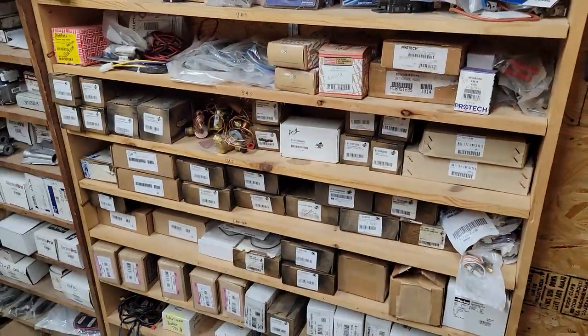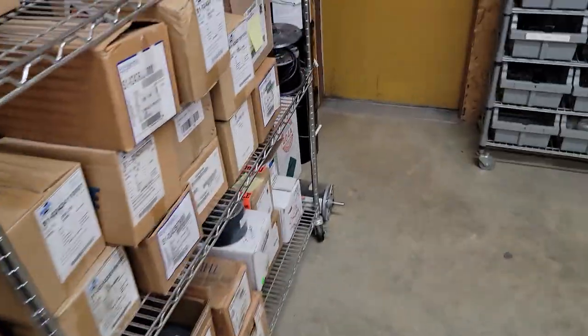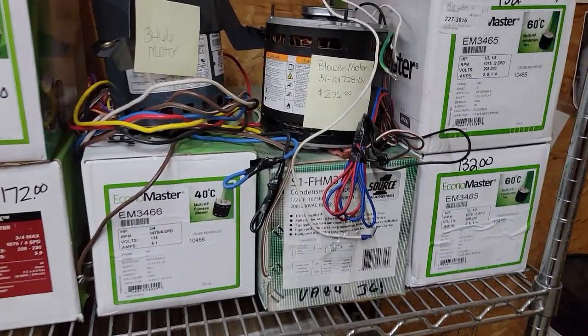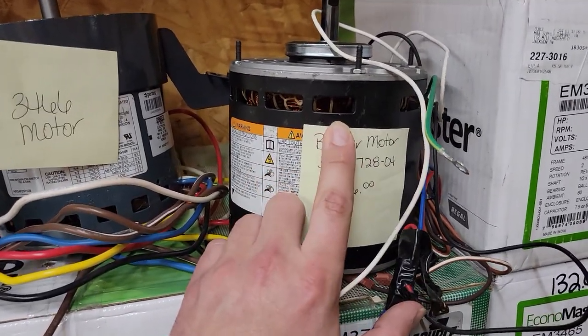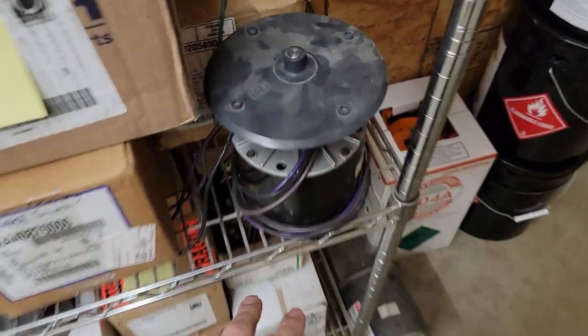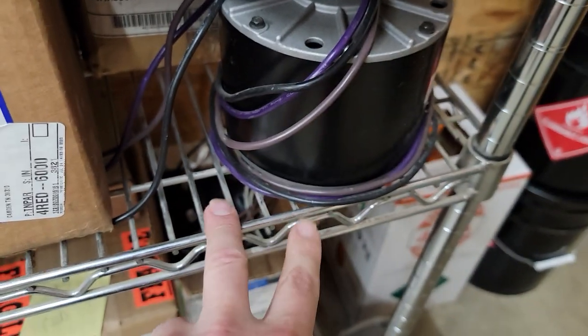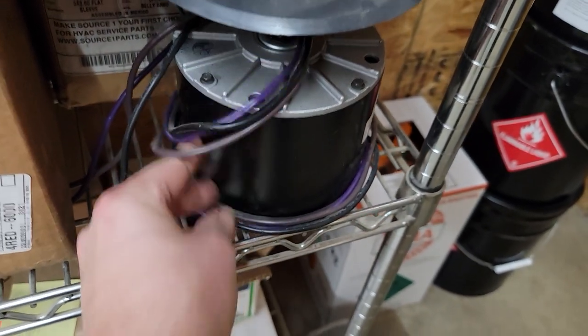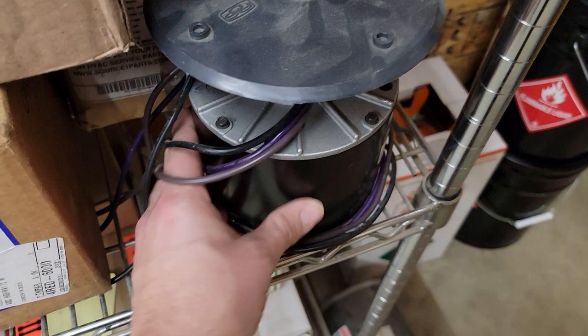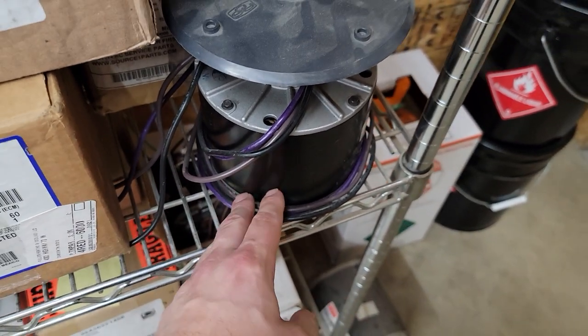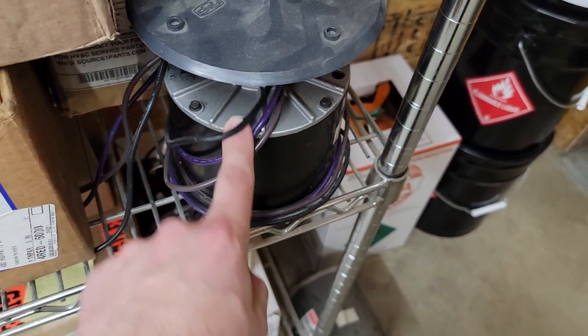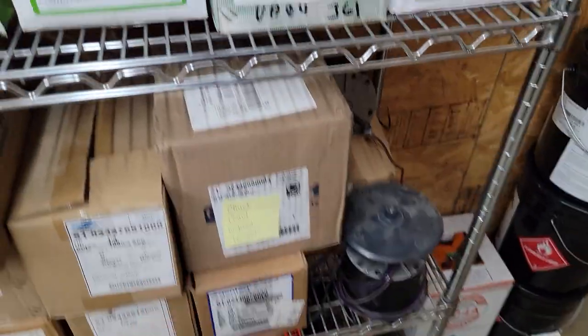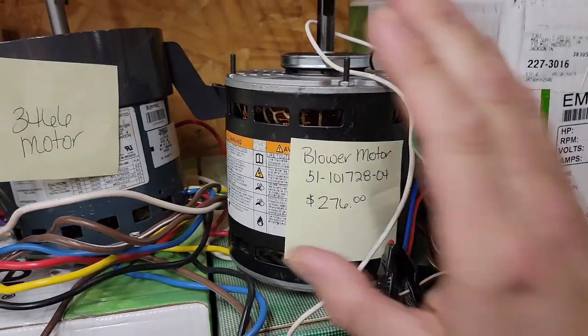All right, let's go over some more parts. First, before we go over some of the winter parts, I'm going to go over some more summer parts. Motors. All right, what's the difference in an open type motor and a closed type motor? This is a condenser fan motor. It's closed type. You can see there's no way for water to get in. This is going to be outside. You have the little drainage holes on the bottom. This is a condenser fan motor. It's an outdoor fan motor. This is an indoor fan motor.